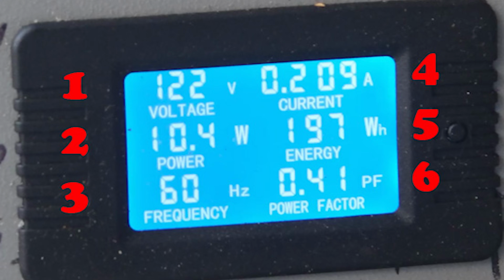The current reflects actual current, so what the device is using, along with the reactive current to give an idea of what the breaker would actually see for a current. I will have to calculate out what the actual consumption of current is because it's actually going to be lower than what box number 4 says, but I'll do that for you guys. Now, number 5 is energy in watt hours. That isn't really too much of a concern. It's just a different way to look at that. And then, of course, number 6 is a calculated power factor.